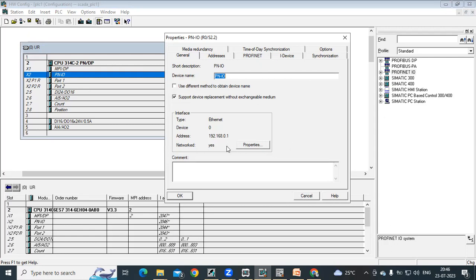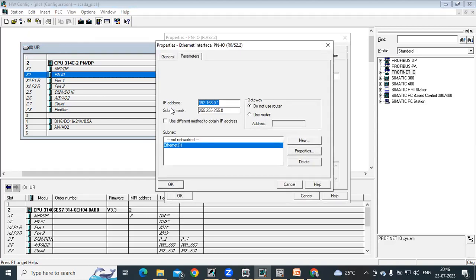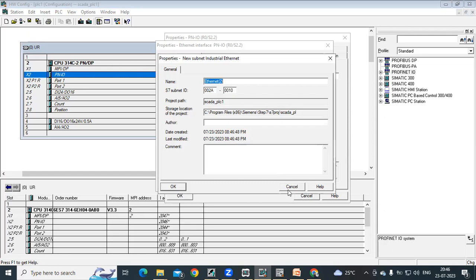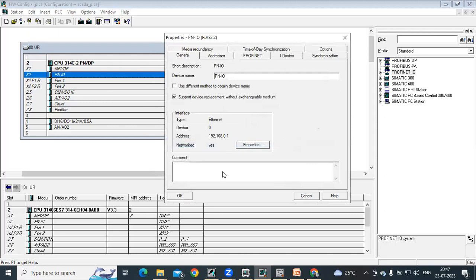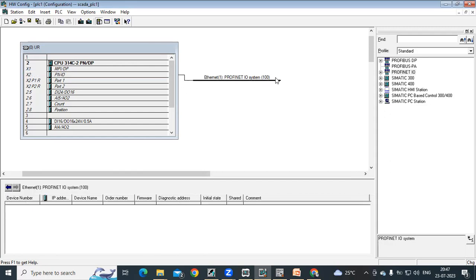In properties, it shows you IP address 192.168.0.1 and under subnet by default it is showing Ethernet. If it is not available, you can click on new to create an Ethernet connection. Once you select, this will be added here and you can select the Ethernet network. Then say okay. Now you can see with this PN IO it is showing one network here. This is your Profinet IO system.